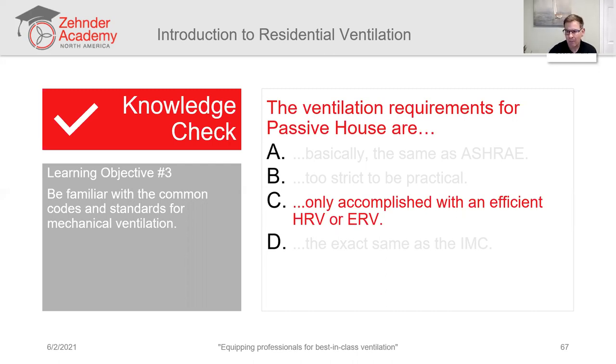Now, we'll note that the standard is very similar. In fact, in Vermont, from the design standpoint, you can use either ASHRAE 62.2-2016, which we briefly covered here, or the Building Science Corporation standard. I think it's 01-2015. Anyway, it's a ventilation standard that Building Science Corporation came up with. Their standard is very basically like the old version of the ASHRAE standard, the one-third version, 0.01 times your square footage. And also in Vermont, you can use the passive house standard as your design basis.